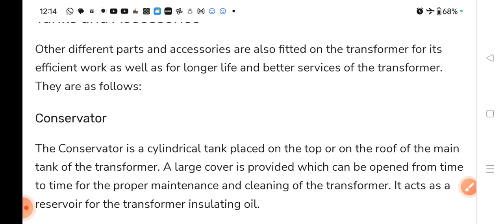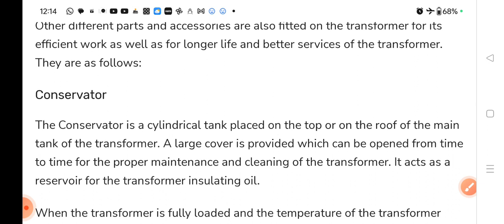The conservator is a cylindrical tank placed on the top roof of the main tank of the transformer. Transformer के ऊपर सबसे top पे हम conservator का use करते हैं. A large cover is provided which can be opened from time to time for the proper maintenance and cleaning of the transformer. It acts as a reservoir for the transformer insulating oil — conservator as a reservoir की तरह काम करता है.